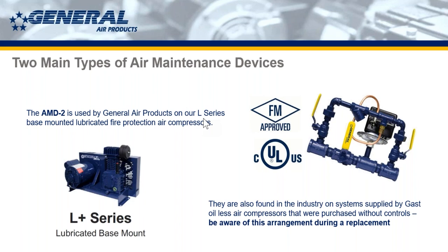You're reading different pressure at different times in a very short period, like a small amount of volume, let's say. So as those pressure fluctuations occur, the pressure switches are telling it to turn on, turn off. You're going to get a lot of crazy cycling and things like that. So, again, there should only ever be one pressure switch hooked up to the compressor. And if you have one of these old AMD2s sitting around, hooked up to a compressor that doesn't have a pressure switch, that's fine until you replace it with a compressor that does have one. So hopefully that makes sense to you, and might save you some headache down the road.